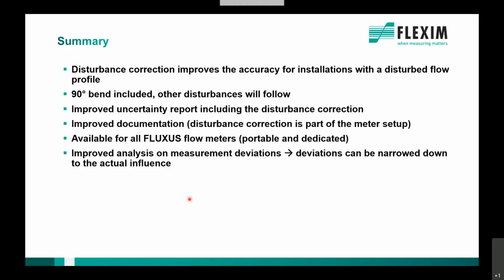It's available for all Fluxus flow meters, for portable and dedicated ones. And as I said, you have an improved analysis of the measurement deviation because you can narrow down to the actual influence, because once you know all the factors, or at least 3 or 4 factors, then you can easily say where the deviation comes from. Before we had 2 more or less unknown factors. Now K Reynolds is defined, is known. That means you can bring it down to the real problem in the field. And that gives you the argument to do so and to find the right explanation.